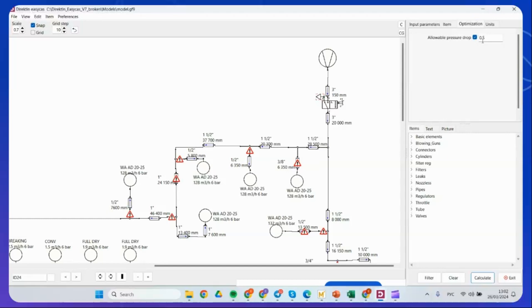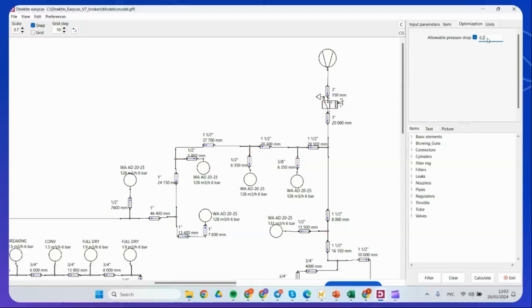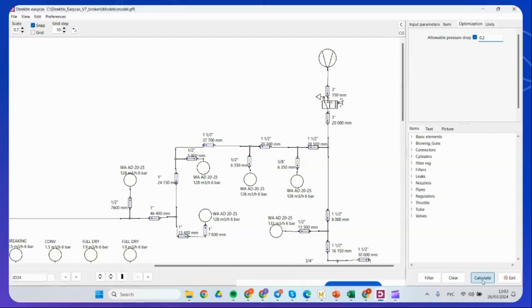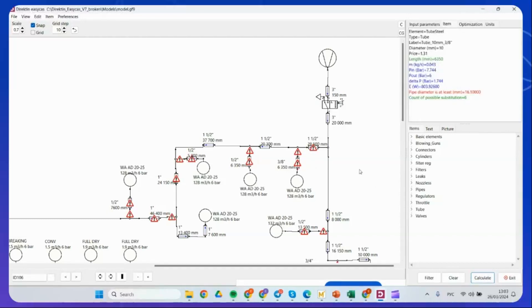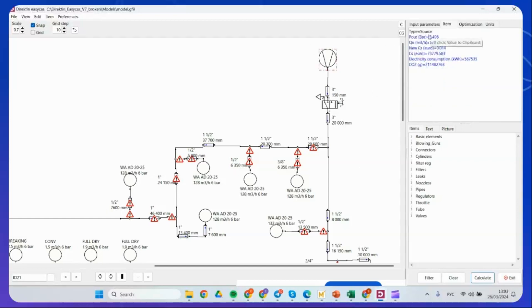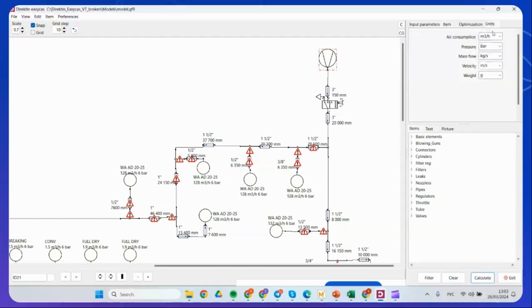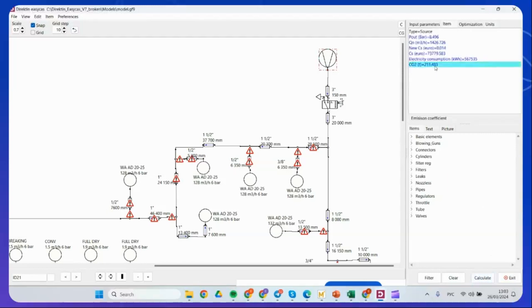After this, one important thing I forgot to mention, optimization criteria. It's the maximum available pressure drop over a component. Of course, half a bar is too much. Let's put 0.2 and now we have this. The program calculates required pressure level at the compressor, required flow rate, also the electricity consumption and CO2 emission. I want it in tons. Yeah, now makes sense. Great.